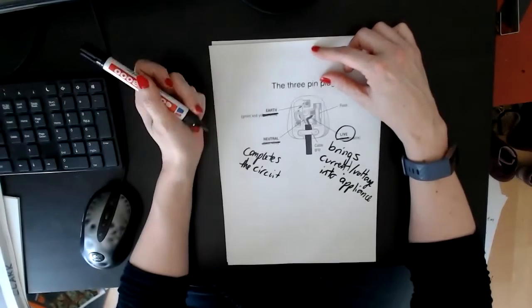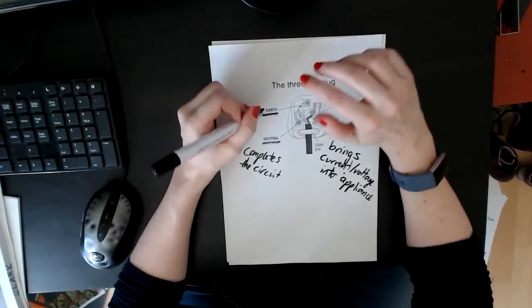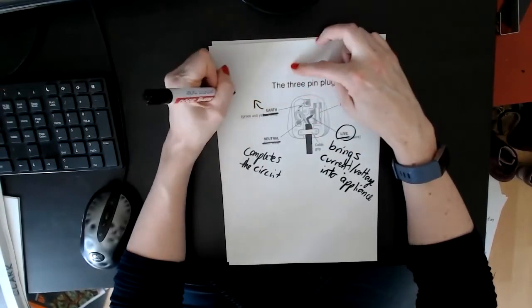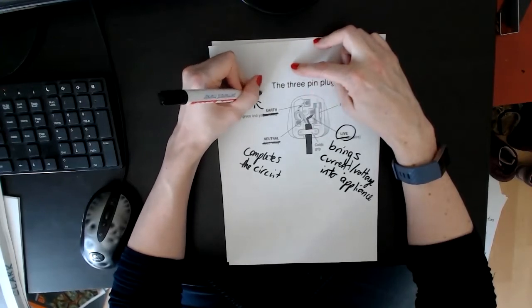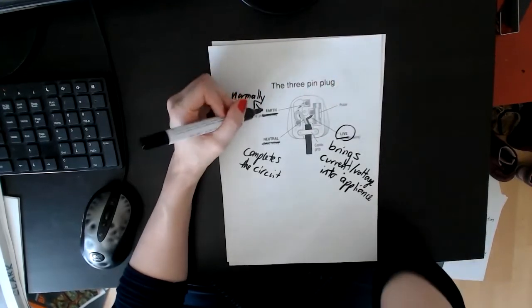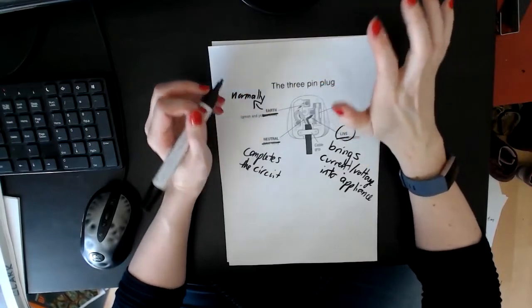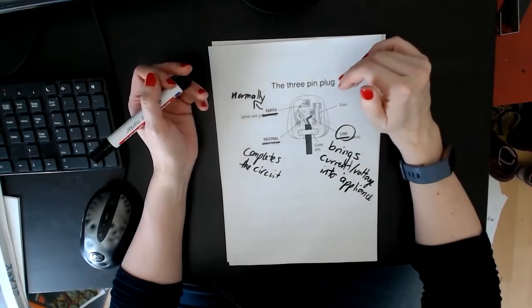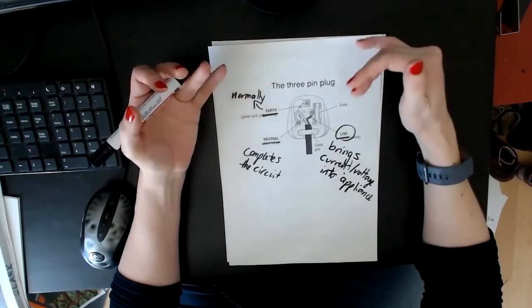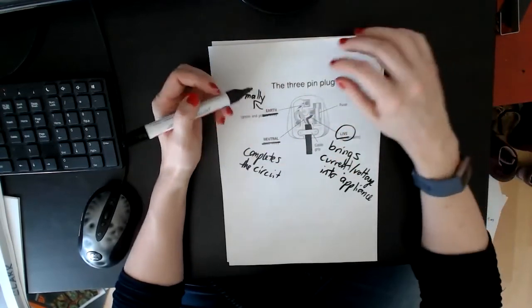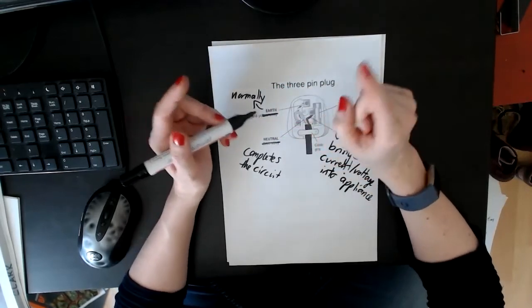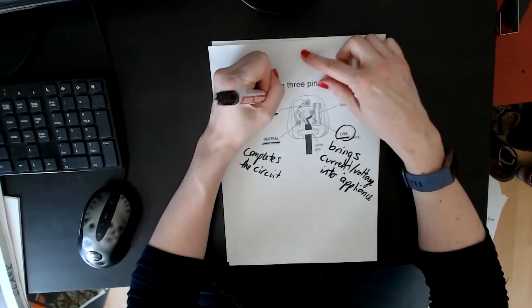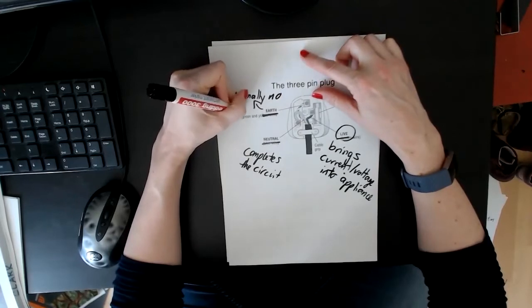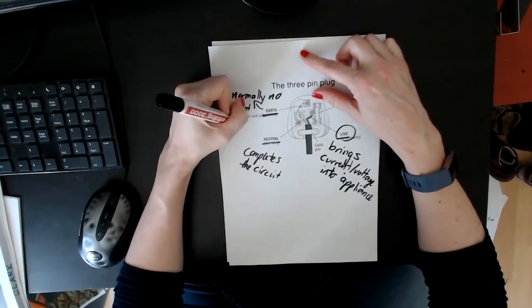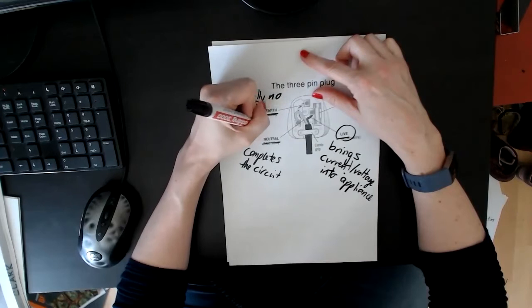The earth wire is a safety feature. Normally it doesn't have any current flowing through it. But if something goes wrong, the idea is that the earth wire provides a low resistance path for the electrons to escape, so that whatever voltage or current there is inside the plug or appliance will go into the earth wire rather than into you, the user. So low resistance path, that's the key part.